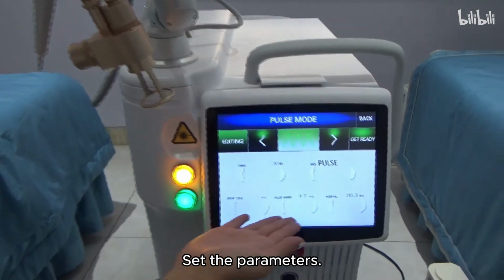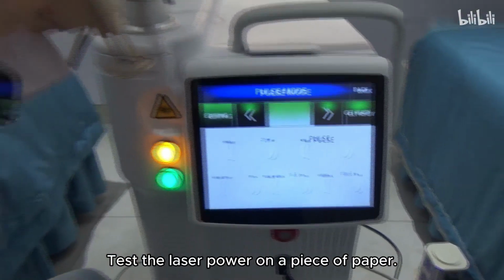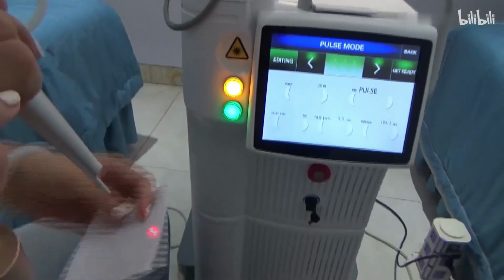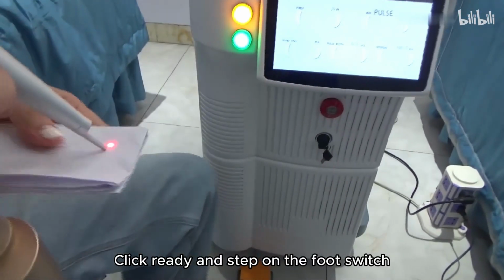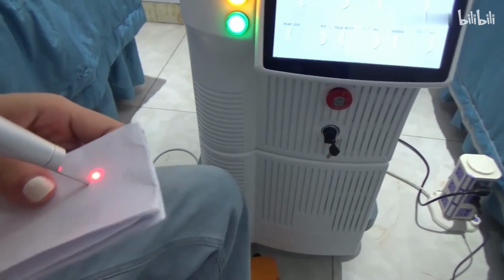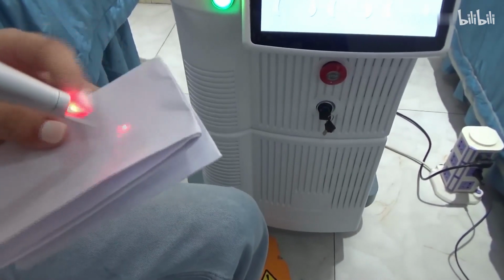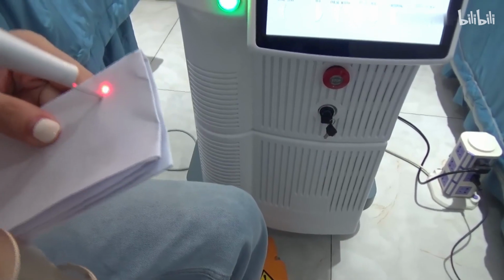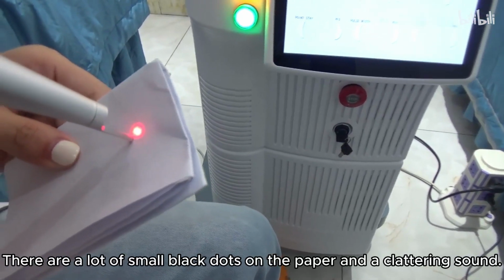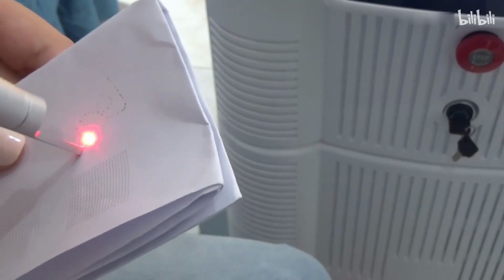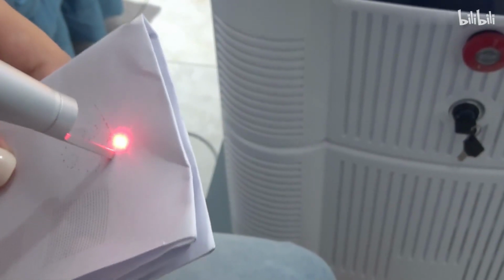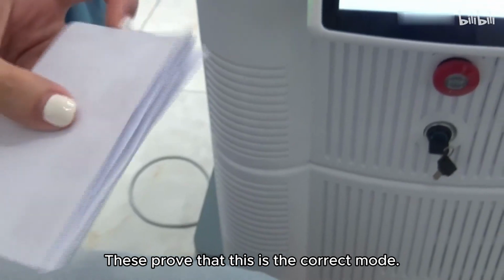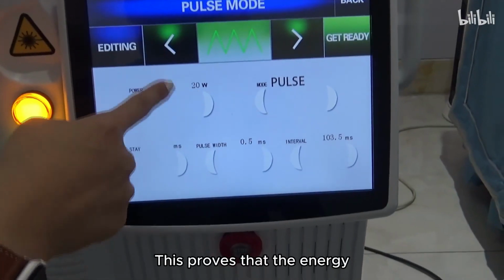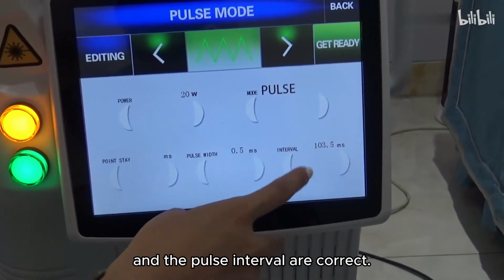Set the parameters. Test the laser power on a piece of paper. Click Ready and step on the foot switch. Wandering on the paper. There are a lot of small black dots on the paper and a clattering sound. These prove that this is the correct mode. No black dots on the back of the paper. This proves that the energy and the pulse interval are correct.